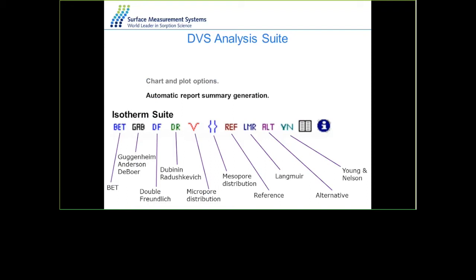The isotherm analysis software offers a range of macros for analyzing and fitting different equations to the isotherm. These include BET surface area, GAB (an extension of the BET equation), the DR macro for micropore/mesopore volume and size distribution using organic vapor, and other equations including Langmuir and Young-Nelson — ideal for determining monolayer or multilayer processes.